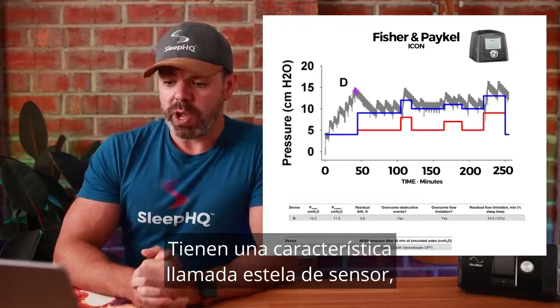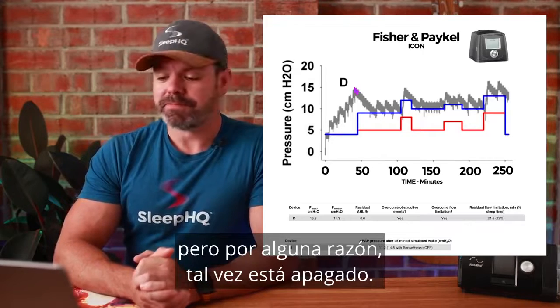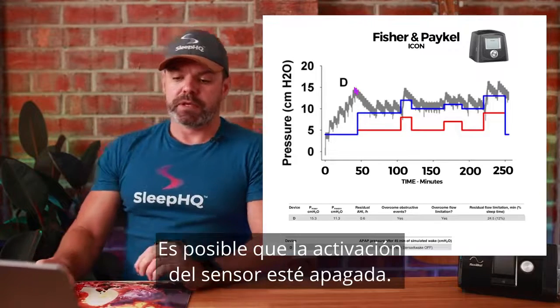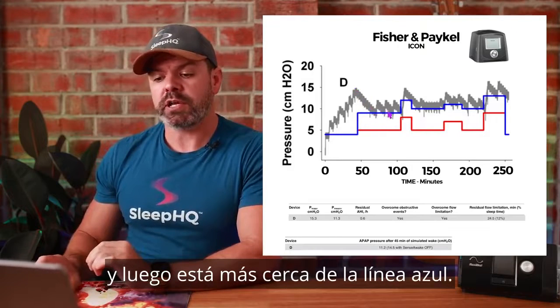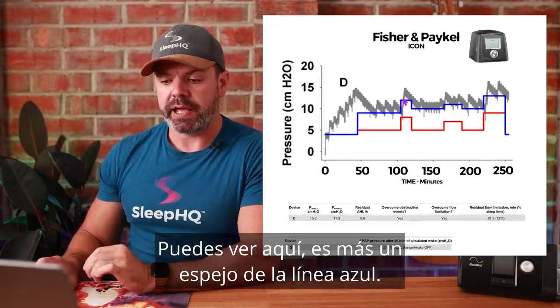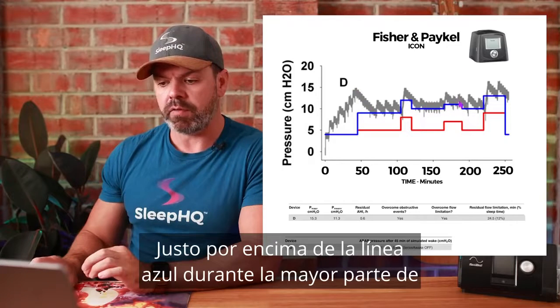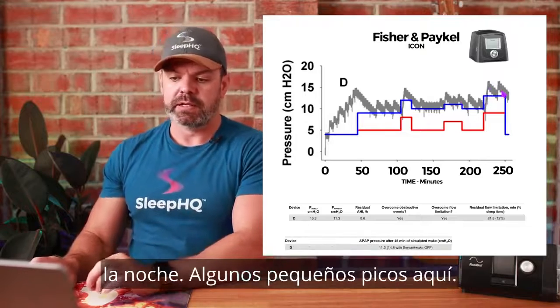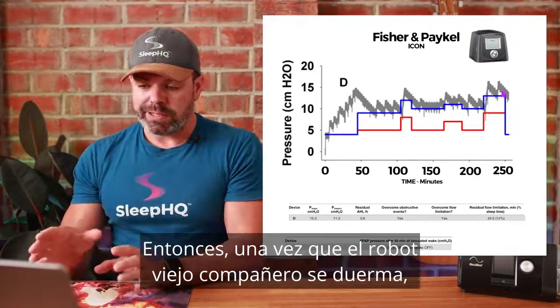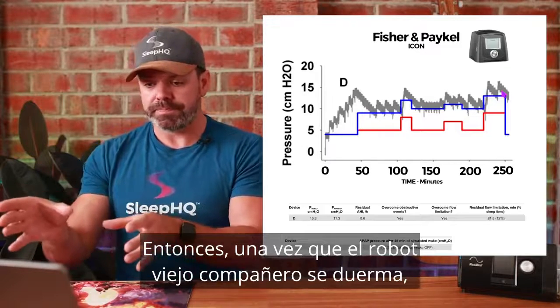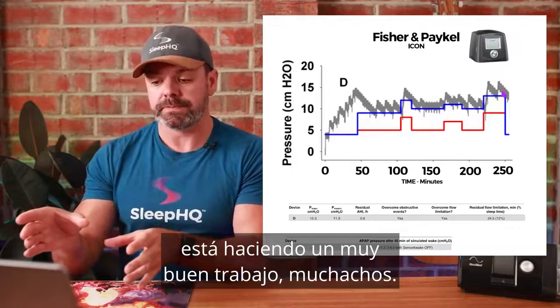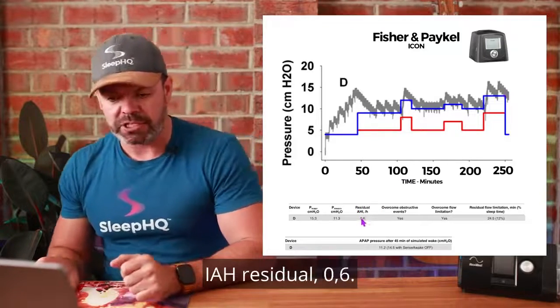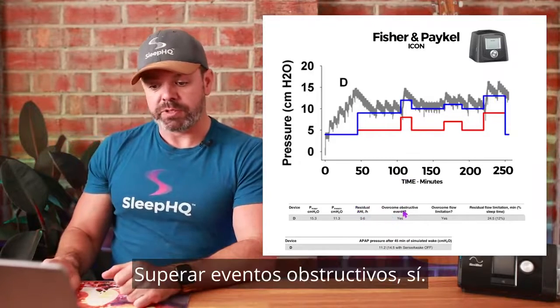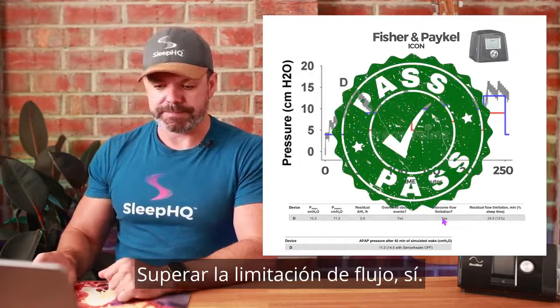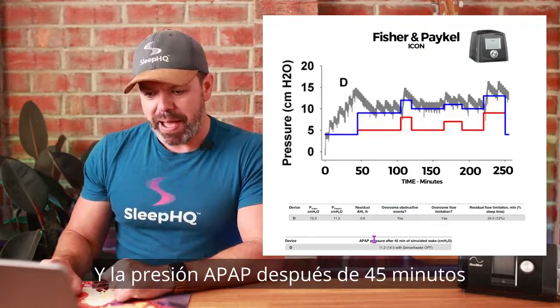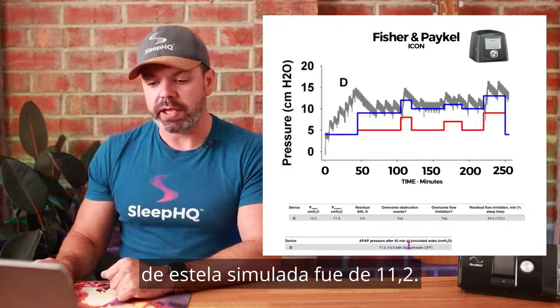So not sure what's going on there. They do have a feature called SensAwake, but for some reason, maybe it's turned off. SensAwake might be turned off. But it quickly comes back down and then it is closer to the blue line. You can see here, it's more of a mirror of the blue line, just above the blue line for most of the night. A few little peaks here. So once old mate robot falls asleep, it's doing a pretty damn good job, guys. All right. If we come down here, residual AHI 0.6, overcome obstructive events, yes. Overcome flow limitation, yes. And the APAP pressure after 45 minutes of simulated wake was 11.2.